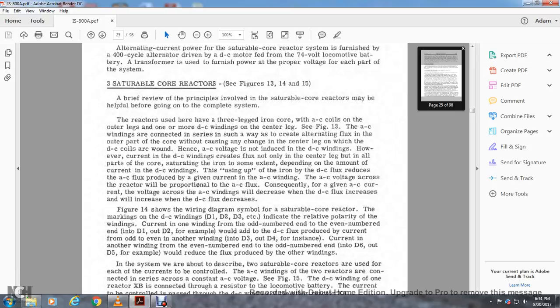Three saturable core reactors: figures 13, 14, and 15. A brief review of the principles involved with the saturable core reactor may be helpful. The reactor has a three-legged iron core with AC coils on the outer legs and one or more DC windings on the center leg. Figure 13 shows the AC winding connected in series so as to create alternate flux in the outer parts of the core without affecting the center leg. The DC coils are wound around the center leg, so AC voltage is not induced in the DC windings. However, current in the DC windings creates flux in the iron not only in the center leg but in all parts of the core, saturating the iron so that the DC flux reduces the AC flux produced by a given current in the AC winding. The AC voltage across the reactor is proportional to the AC flux.